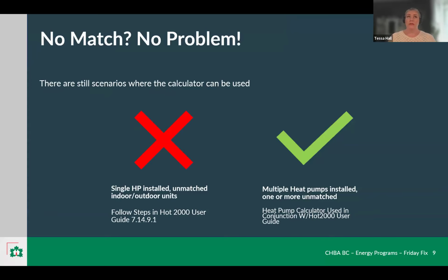Sometimes you'll run into scenarios where your outdoor unit and indoor unit are not matched properly - you don't have an AHRI certificate of matched units for those projects. If the home only has the one heating system, and that's the only system present in the house, it's going to get described as an unmatched system, where you have a unit outside that's, say, one brand, and an indoor unit that's another brand. For those, you follow the steps in the Hot 2000 user guide and put it at its default settings - we'll talk about that more later. But if it's a single unit like that, you have a procedure to follow, and it does not need the calculator.